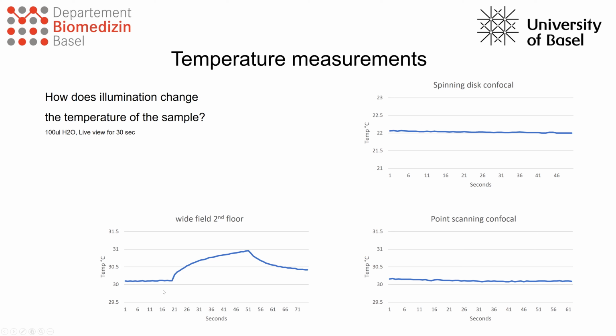And we saw that in wide field cases the temperature can go slightly up, so it increased not a degree but almost a degree, while on point scanning confocal but also on spinning disk confocals the temperature didn't increase at all. So this was also a little bit surprising because I was expecting the opposite, to be honest. But this is probably due to the fast scanning and also that we only illuminate a small point, while on a wide field system you illuminate a larger area at a time, and if you then have it live for like 30 seconds, that's still quite a long time. So that's at least what we assumed.